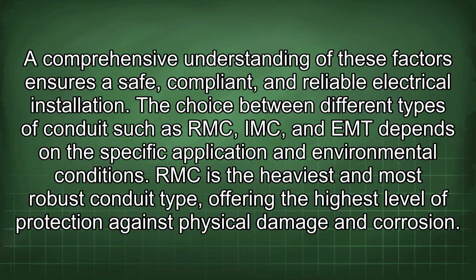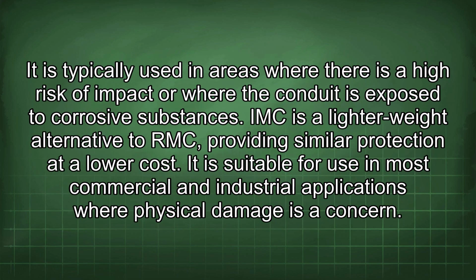The choice between different types of conduits such as RMC, IMC, and EMT depends on the specific application and environmental conditions. RMC is the heaviest and most robust conduit type, offering the highest level of protection against physical damage and corrosion. It is typically used in areas where there is a high risk of impact or where the conduit is exposed to corrosive substances. IMC is a lighter weight alternative to RMC, providing similar protection at a lower cost.